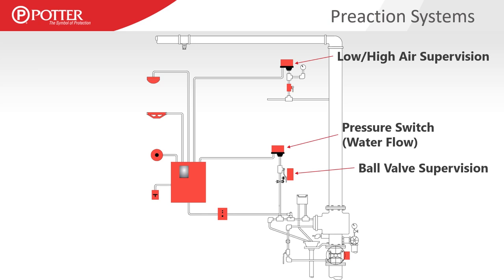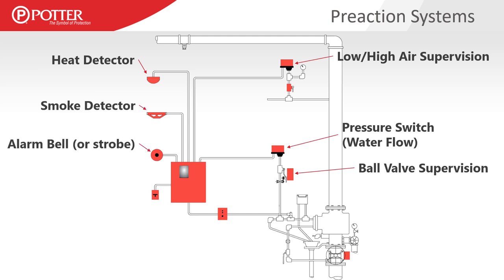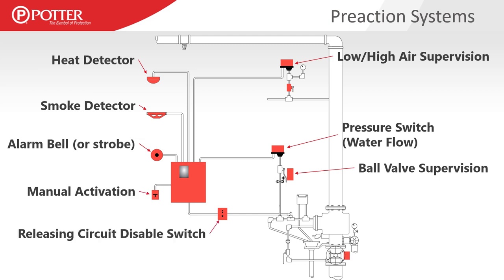Ball valve supervision is again important — if we have a ball valve in line before the pressure type flow switch, we need to supervise that valve to keep it from being inadvertently left shut. Pre-action systems also include fire alarm devices such as heat detectors, smoke detectors, alarm bells or strobes tied to the activation of the system, manual activation and manual releasing or disable switches. Any valve that controls water supply to any of these systems has to have that valve supervised.